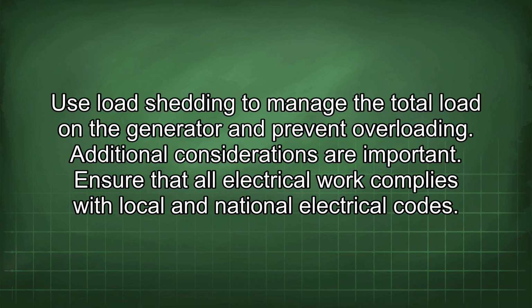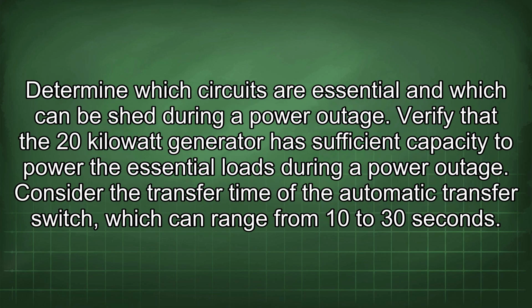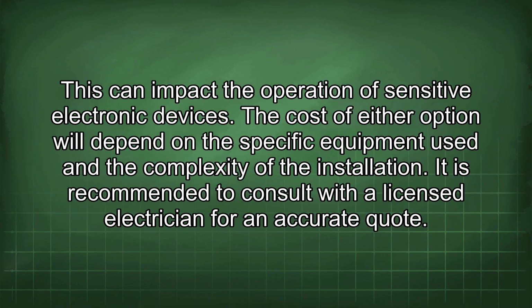Additional considerations are important. Ensure that all electrical work complies with local and national electrical codes. Determine which circuits are essential and which can be shed during a power outage. Verify that the 20 kilowatt generator has sufficient capacity to power the essential loads during a power outage. Consider the transfer time of the automatic transfer switch, which can range from 10 to 30 seconds. This can impact the operation of sensitive electronic devices. The cost of either option will depend on the specific equipment used and the complexity of the installation. It is recommended to consult with a licensed electrician for an accurate quote.